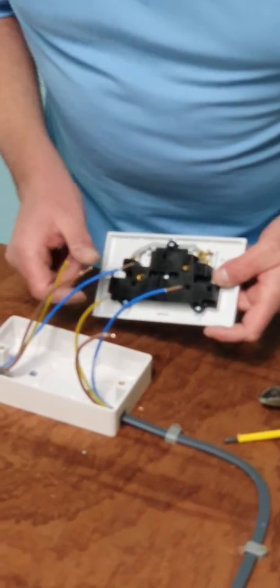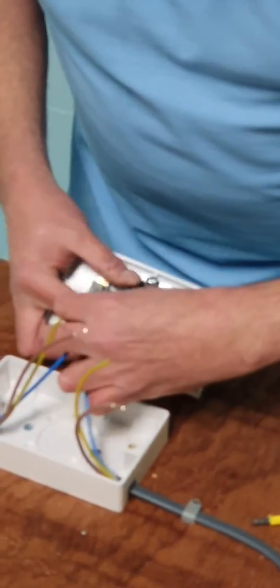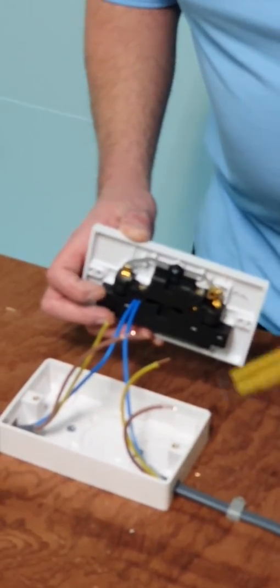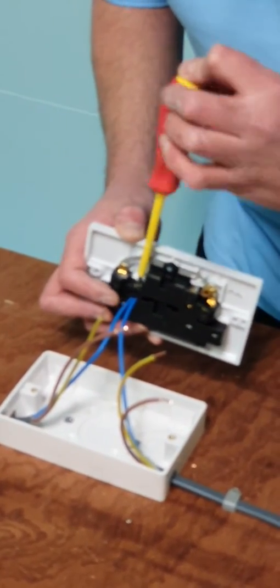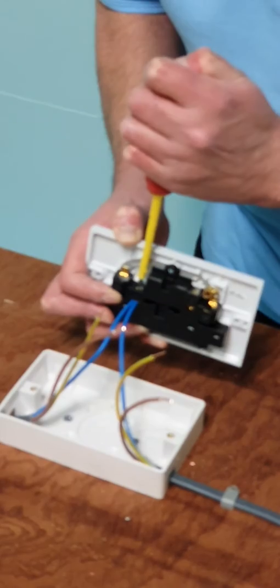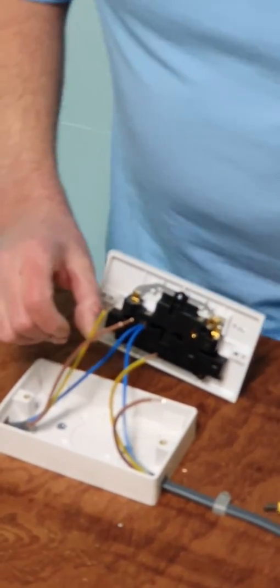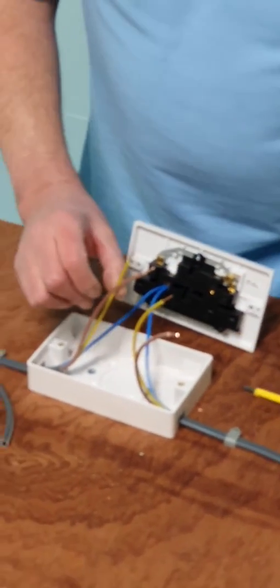And I'll try and do this the other way. So this side here we have neutrals. So bring our neutrals together. Slide them into our neutral terminal. Notice that we haven't got any copper exposing outside the terminal. That little creak there is just saying that we're tight enough. Don't want to be too tight. You're at risk of snapping these screws and also damaging the conductors.